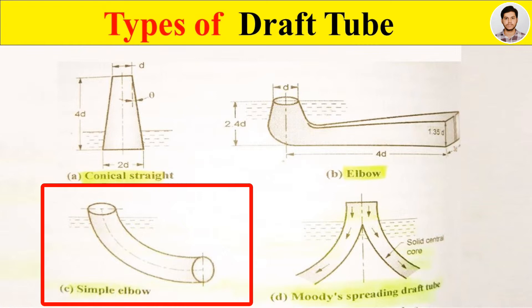Next is a simple elbow draft tube. It has circular cross section throughout from inlet to outlet, as shown in the figure. Elbow type draft tubes are used for Kaplan turbines. It is made up of concrete with steel lining at inlet. Such draft tube has efficiency up to 60 percent.